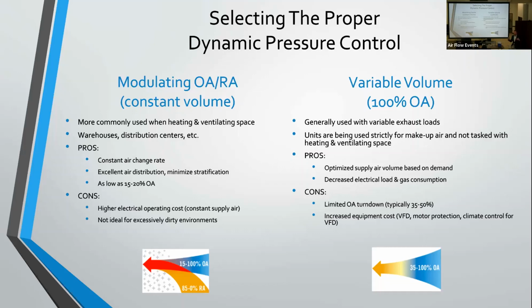So when your building's sealed up and all your doors are shut, your outside air dampers modulate closed, just closed enough to maintain a positive pressure in the space. And all you're really trying to do is overcome the infiltration on the envelope. As your doors open up, you create a really big infiltration opening, so it requires more outside air to pressurize that space. Your outside air dampers modulate open. Same thing when the door is shut. So they're constantly modulating back and forth to maintain that 0.01, 0.02.